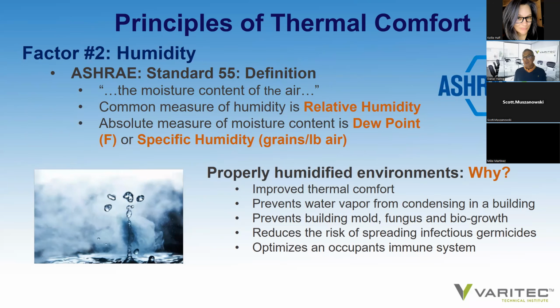However, Standard 62.1 is moving away from relative humidity per the 2019 standard and is moving to dew point. And the reason why it's moving to dew point is that, unlike relative humidity, that is relative to the temperature of the air in which the moisture is contained, dew point and specific humidity are independent of temperature, so they're referenced as absolute measures of moisture content in the sample of air. Well, why do we need to control humidity in an environment? Well, it's to improve thermal comfort for reasons we'll express shortly.